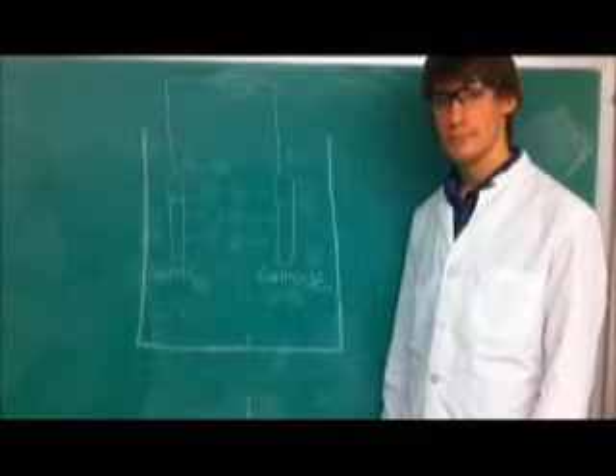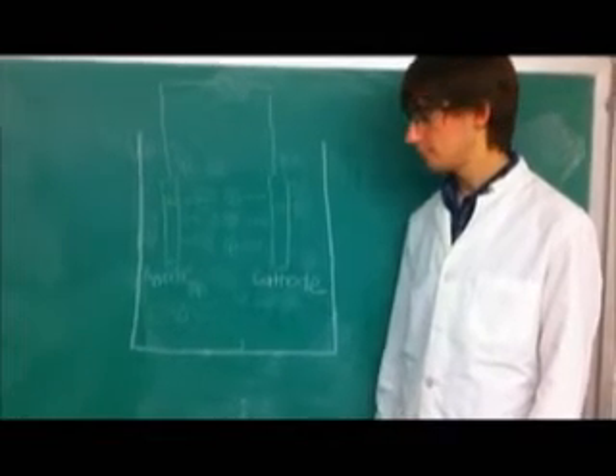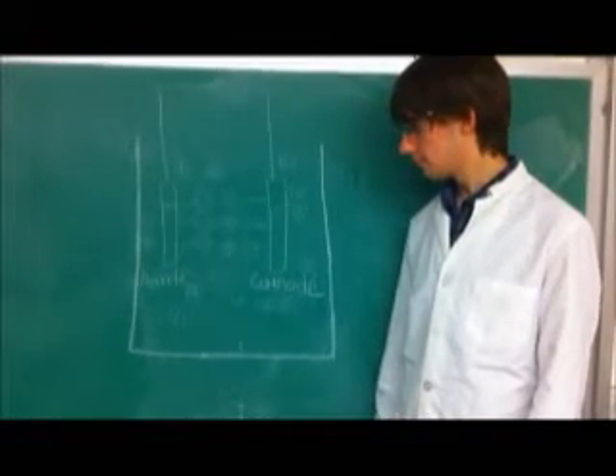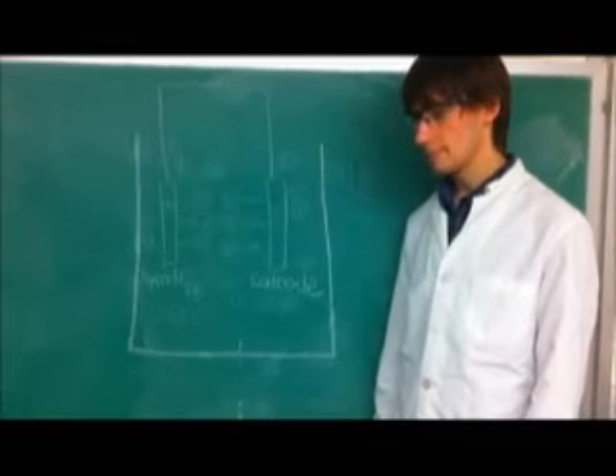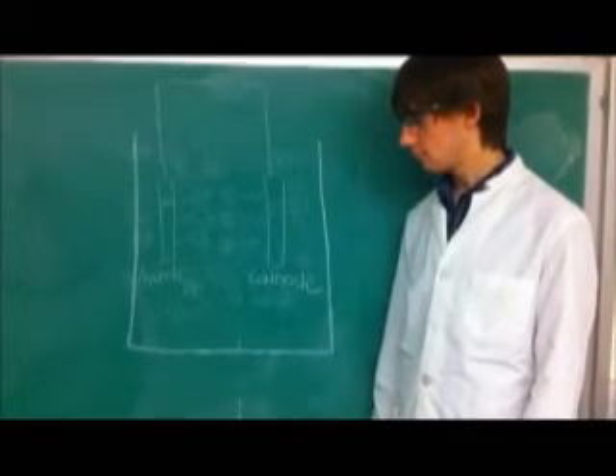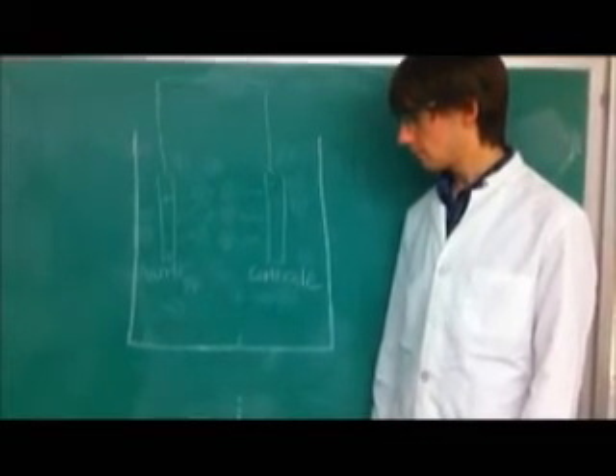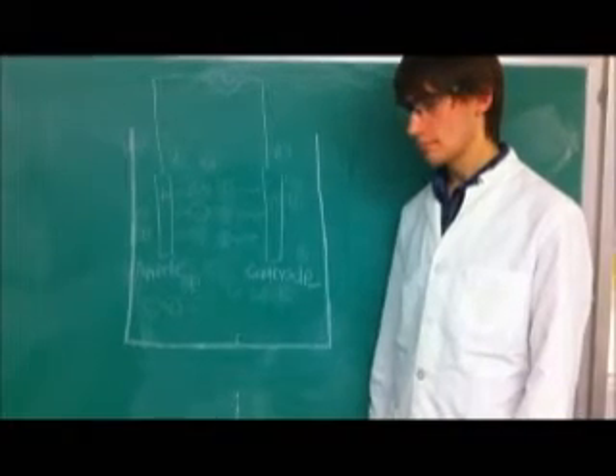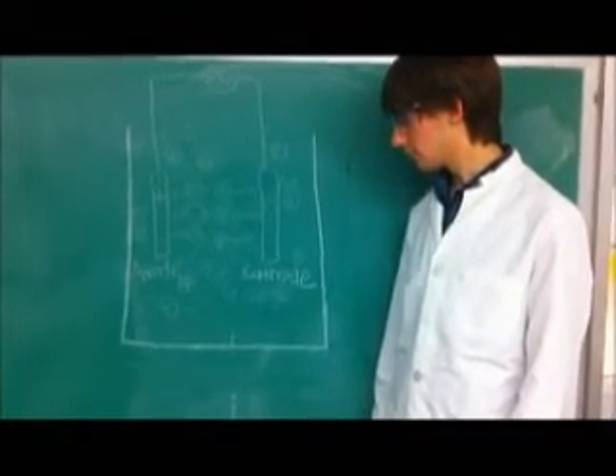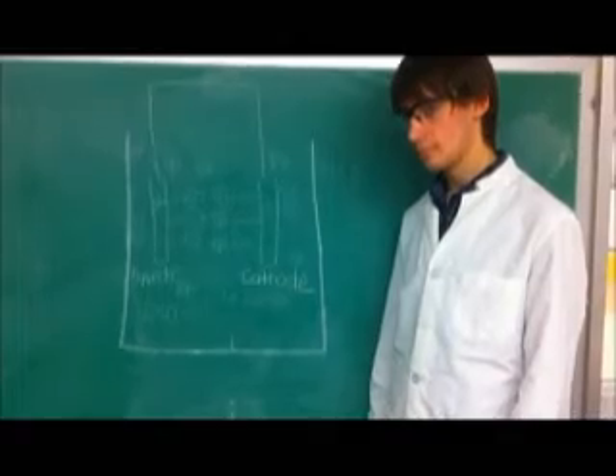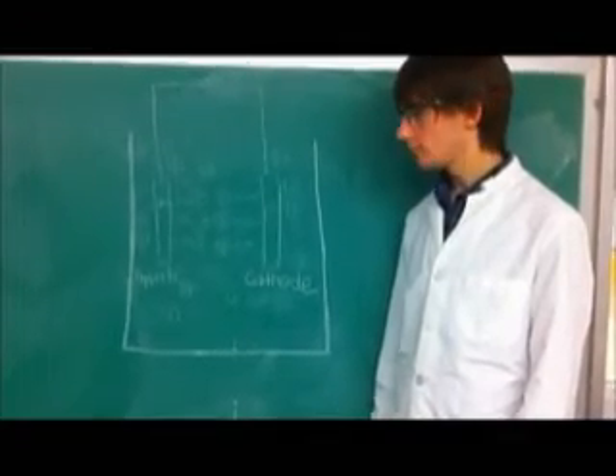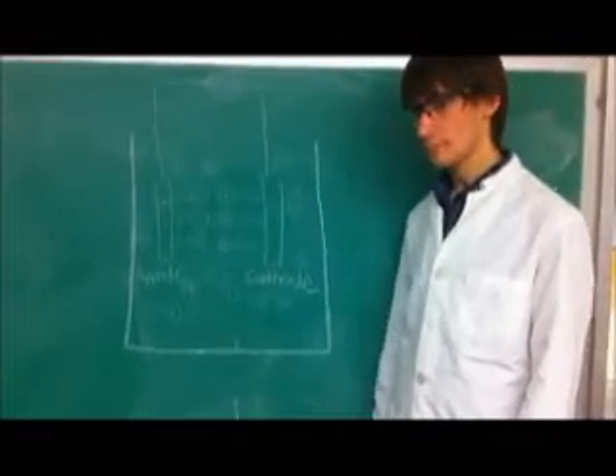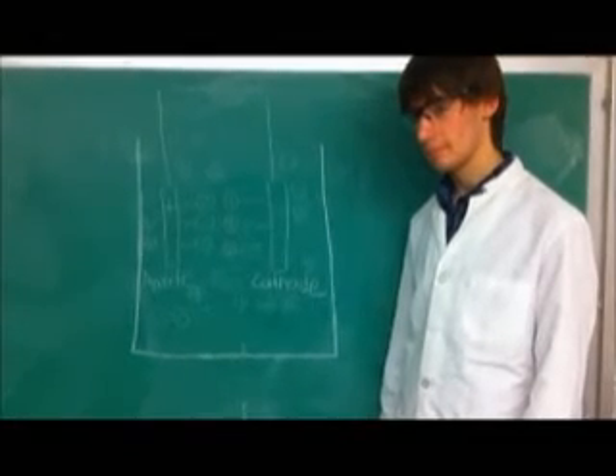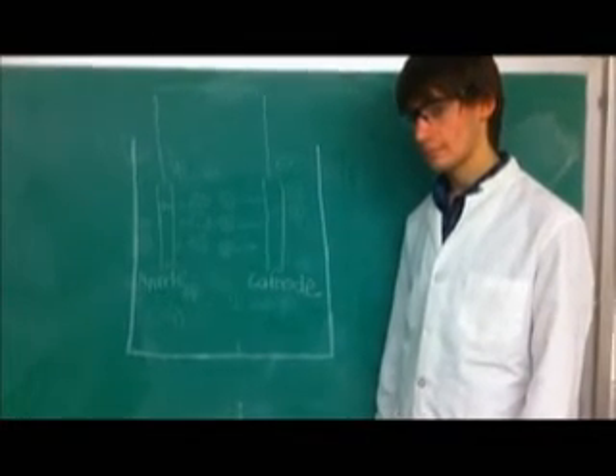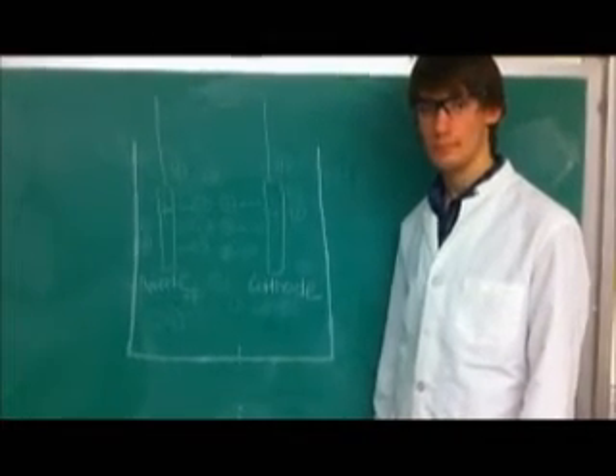Negative electron-carrying ions move toward the anode. Positive electron-less ions move towards the cathode. Their electrons are taken from them, and they become positive and start moving toward the negative cathode. At the cathode, they are given an electron, and the process repeats. What the computer measures is the conductivity of the solution by measuring the amount of current, proportional to the ion concentration, when a potential difference is applied between the two parts of the probe.